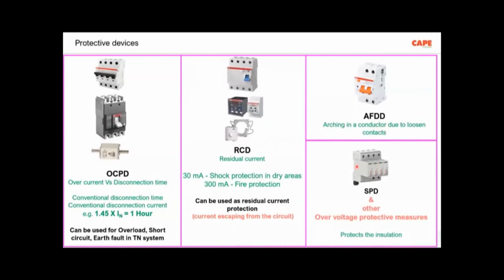Then the next protective device which is required in your network is the SPD, surge protective device, and I have put other overvoltage protective measures. And these protective measures actually protect your insulation. Are we using SPDs in every electrical installation? This is quite less. I would say not much. Only in a few places are SPDs used. But the next point, other overvoltage protective measures, is very, very important.